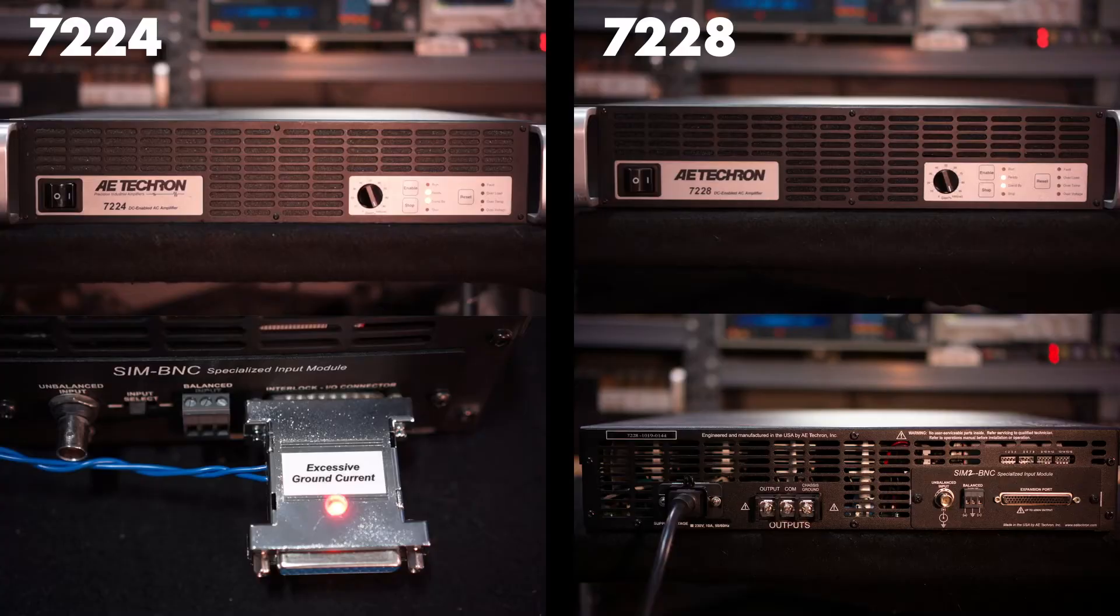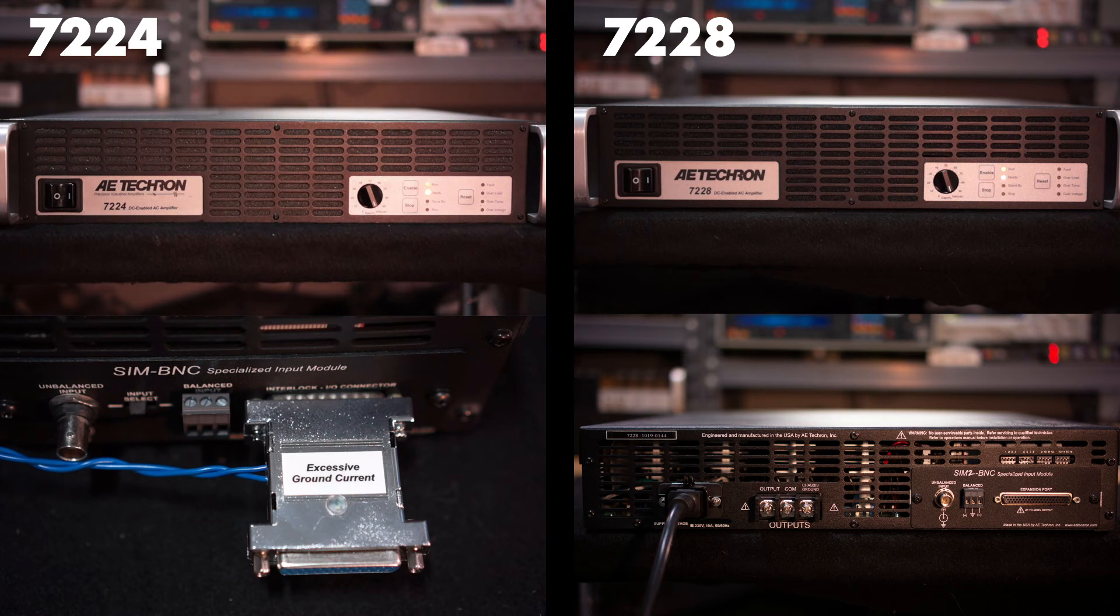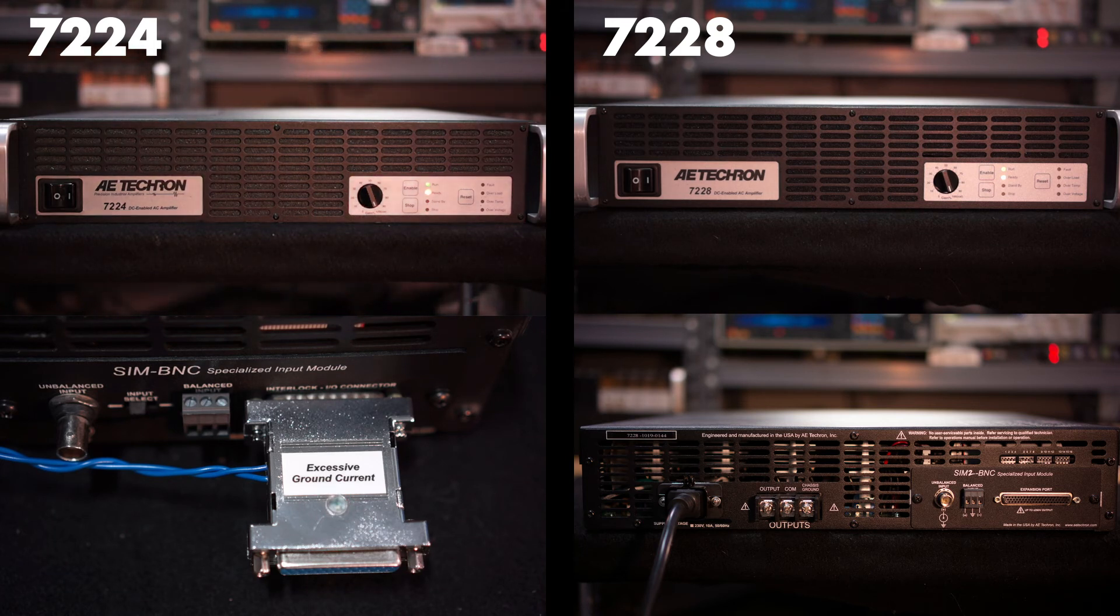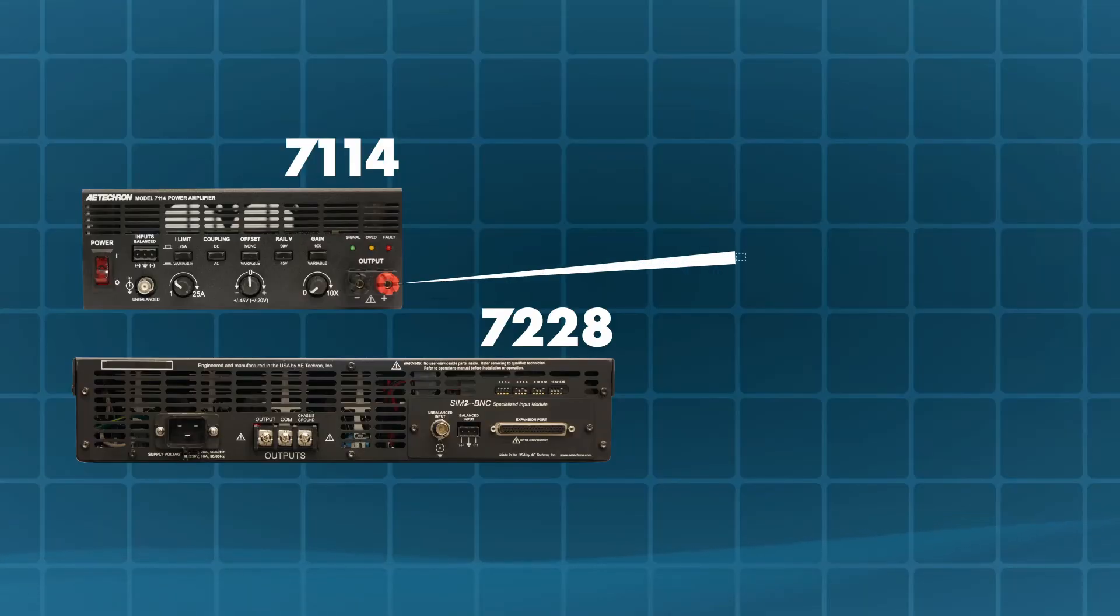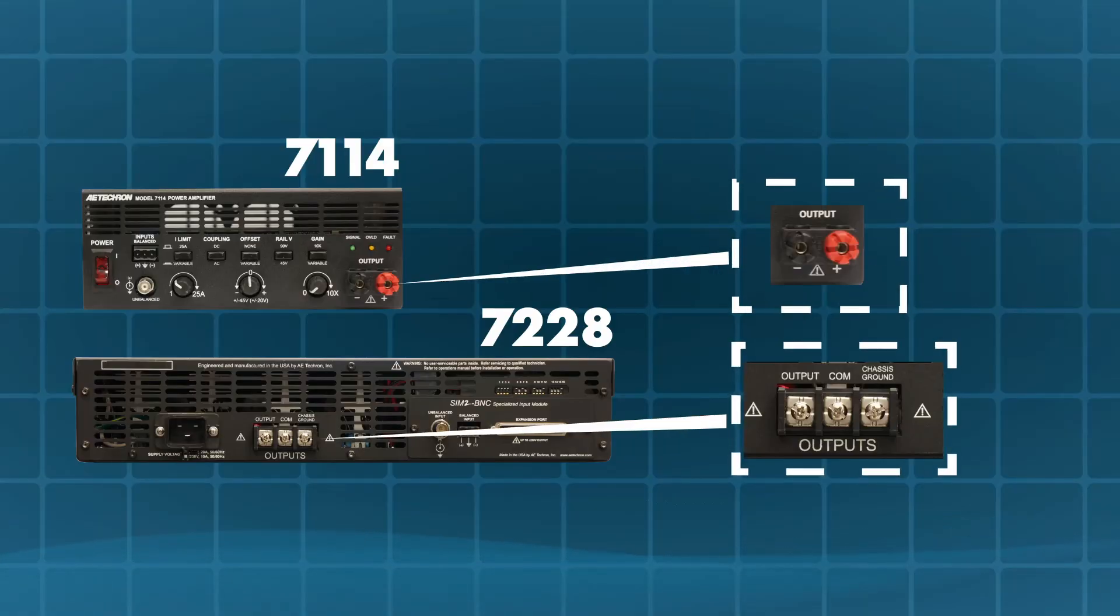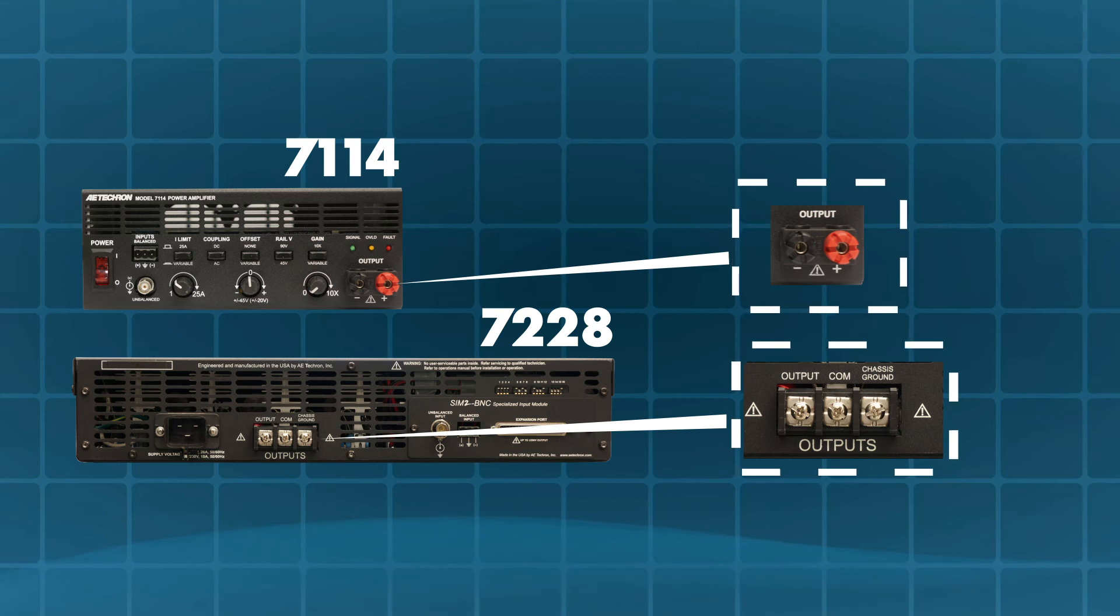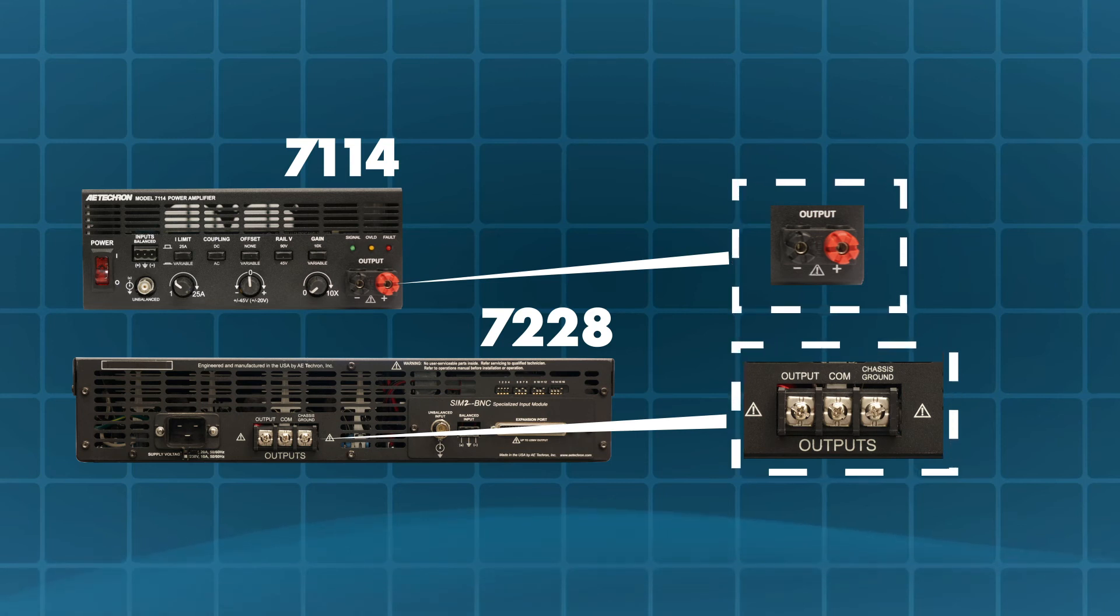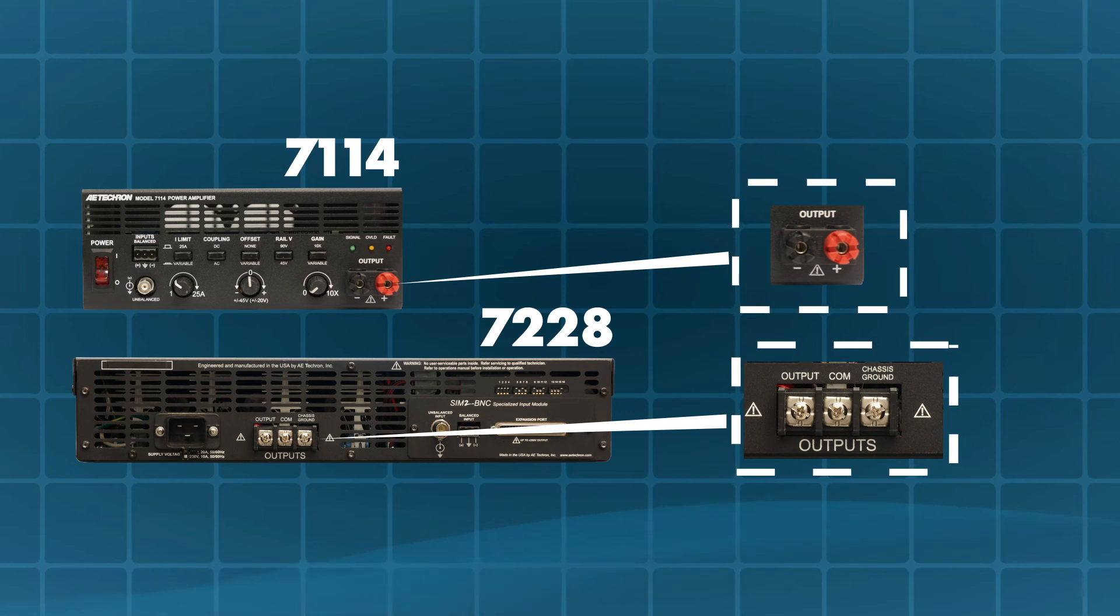This internal circuitry, like the external GCL accessory, will automatically place the amplifier in standby should a ground loop occur and will automatically return the amplifier to a run state when the ground loop or excessive ground current condition is passed. On models that use internal circuitry for ground loop protection, there is no external conductor or resistor used. This internal circuitry rarely needs repair or replacement due to its robust design and self-resetting capability.